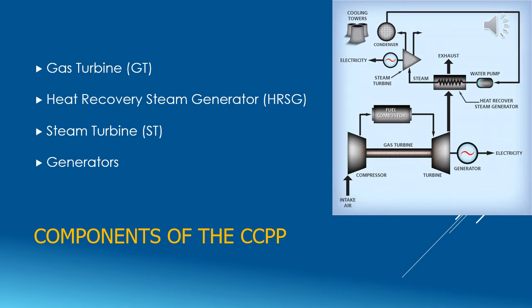The components of the combined cycle power plant are the gas turbine, the heat recovery steam generator, also known as the HRSG, the steam turbine, and the generator. The gas turbine uses air as its working fluid and burns fuel in the combustion chamber to generate hot gas, and this force is used to turn the turbine connected to the generator. The HRSG removes exhaust heat from the gas turbine and uses water to convert it to superheated steam to drive the steam turbine. This driving force from the HRSG connected to the generator creates an additional power output.